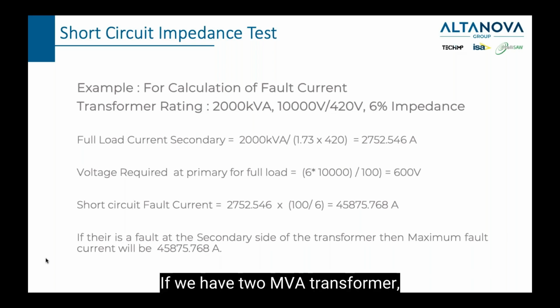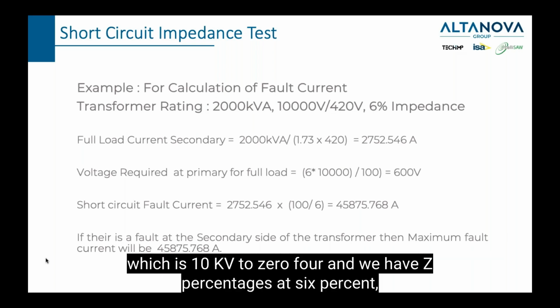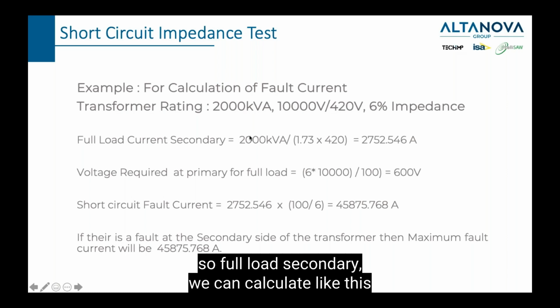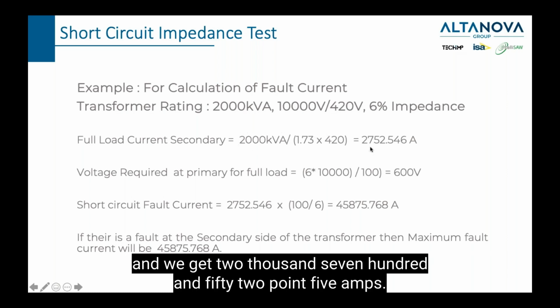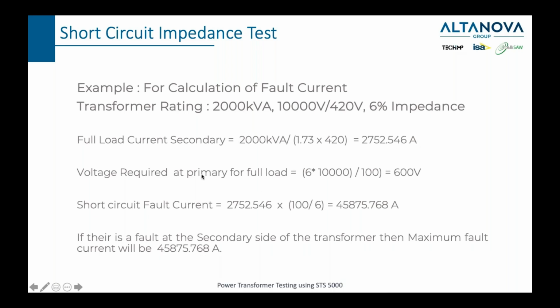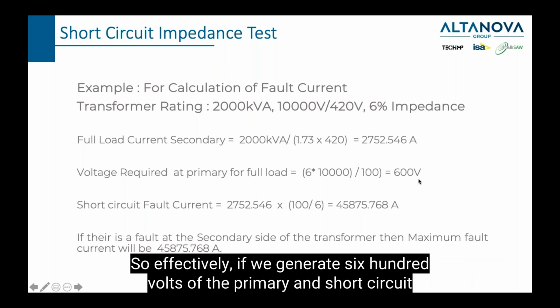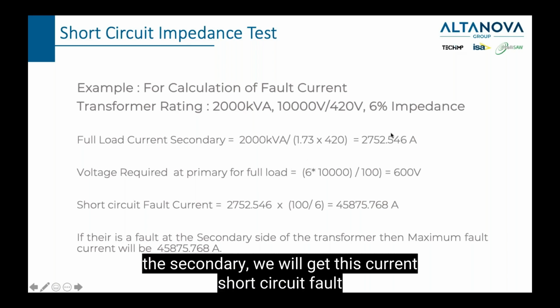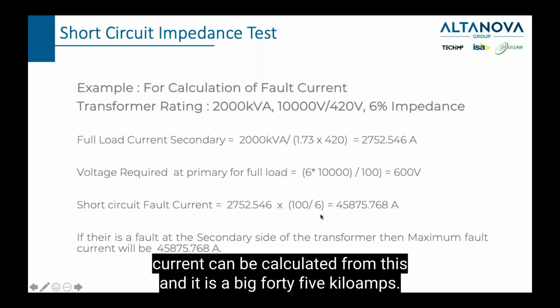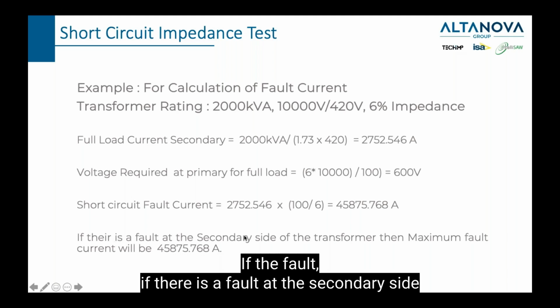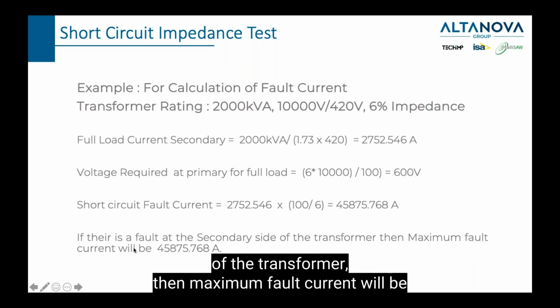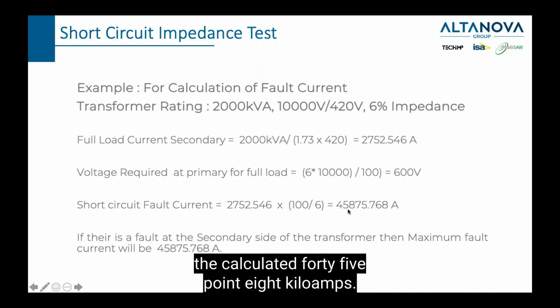One example here: if we have a 2 MVA transformer, which is 10 kV to 0.4, and we have Z percentage at 6%. So the full load secondary current we can calculate like this, and we get 2,752.5 amps. The voltage required at primary for full load, because it's only 6% of primary voltage, is 600 volts. So effectively, if we generate 600 volts on the primary and short circuit the secondary, we will get this current. Short circuit fault current can be calculated from this, and it is a big 45 kiloamps. If there is a fault at the secondary side of the transformer, then the maximum fault current will be the calculated 45.8 kiloamps.